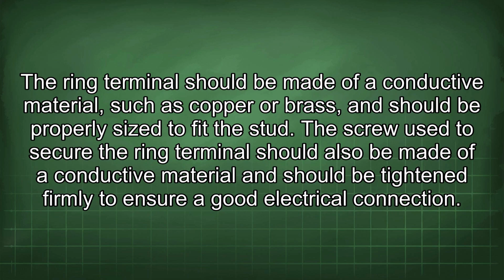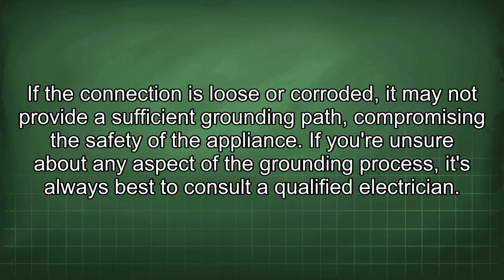The ring terminal should be made of a conductive material, such as copper or brass, and should be properly sized to fit the stud. The screw used to secure the ring terminal should also be made of a conductive material and should be tightened firmly to ensure a good electrical connection. If the connection is loose or corroded, it may not provide a sufficient grounding path, compromising the safety of the appliance. If you're unsure about any aspect of the grounding process, it's always best to consult a qualified electrician.